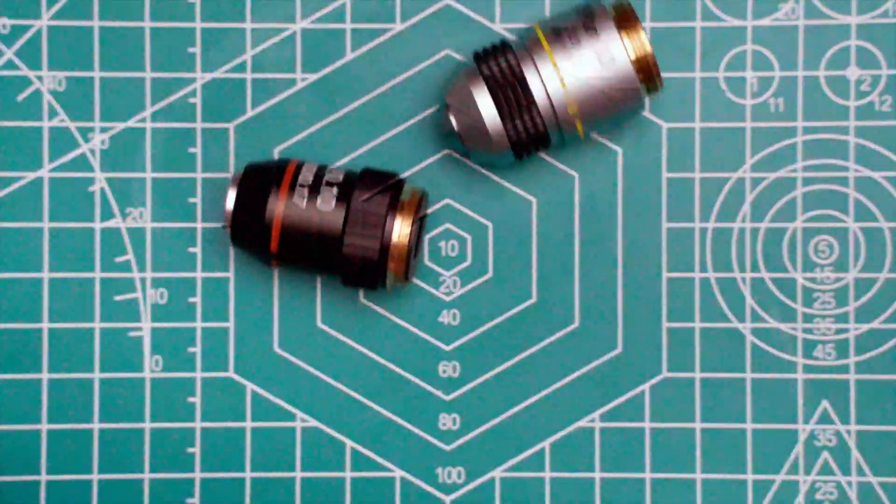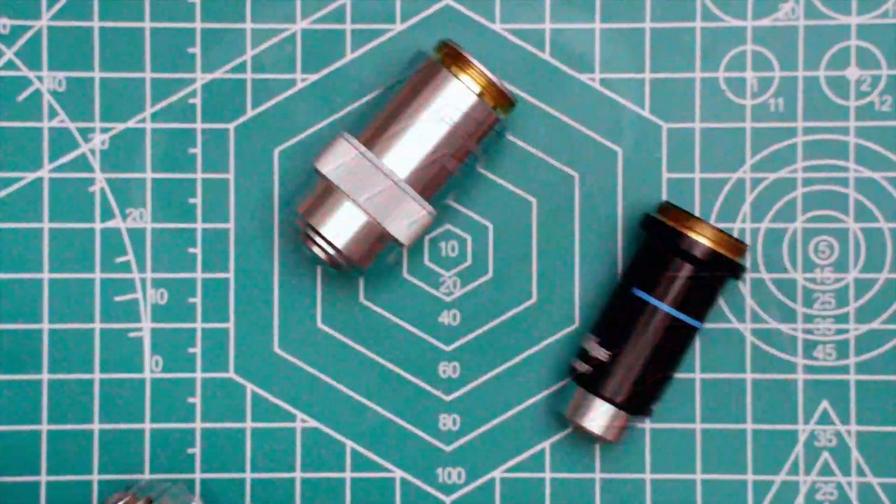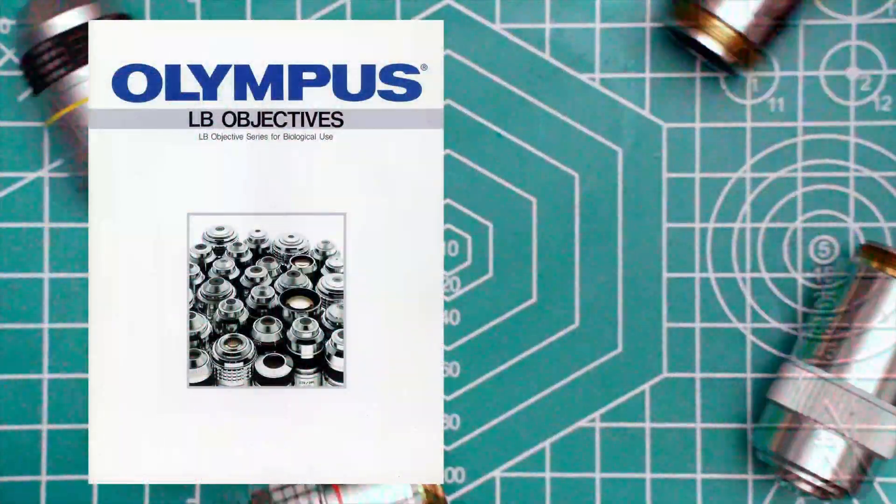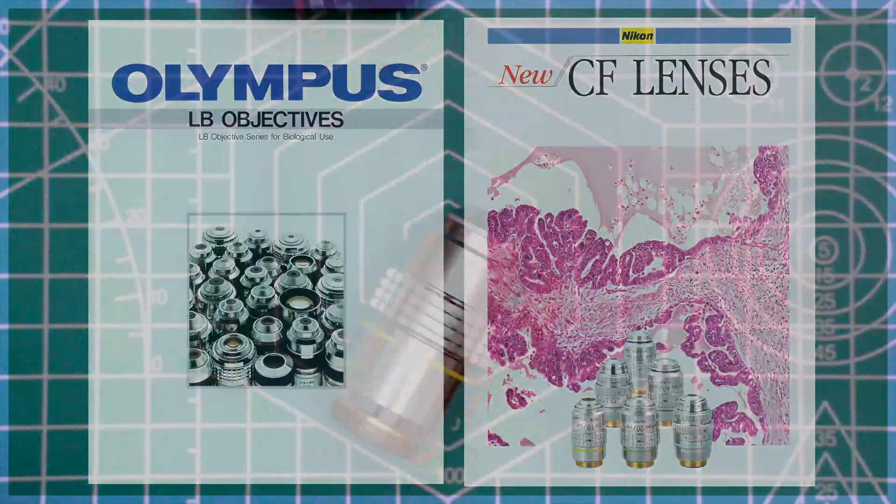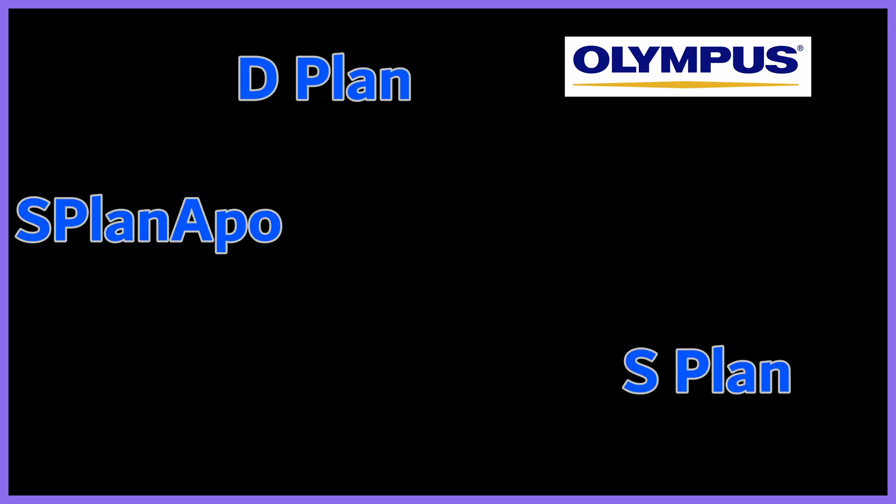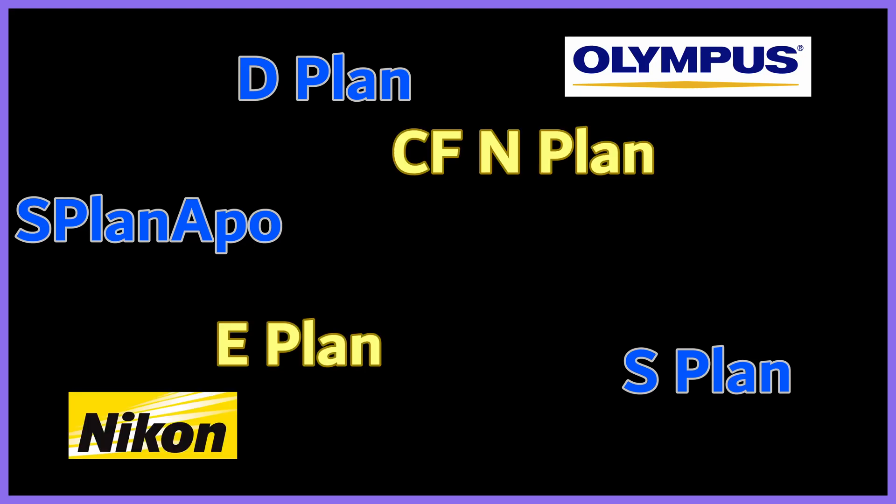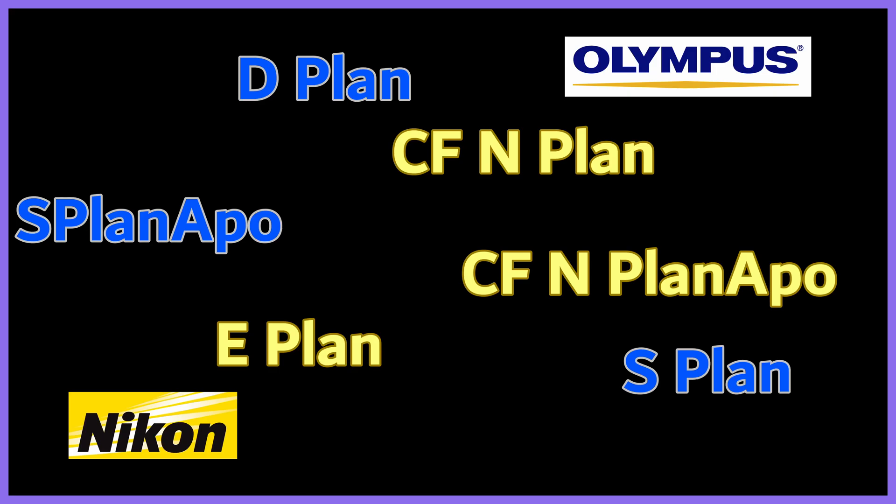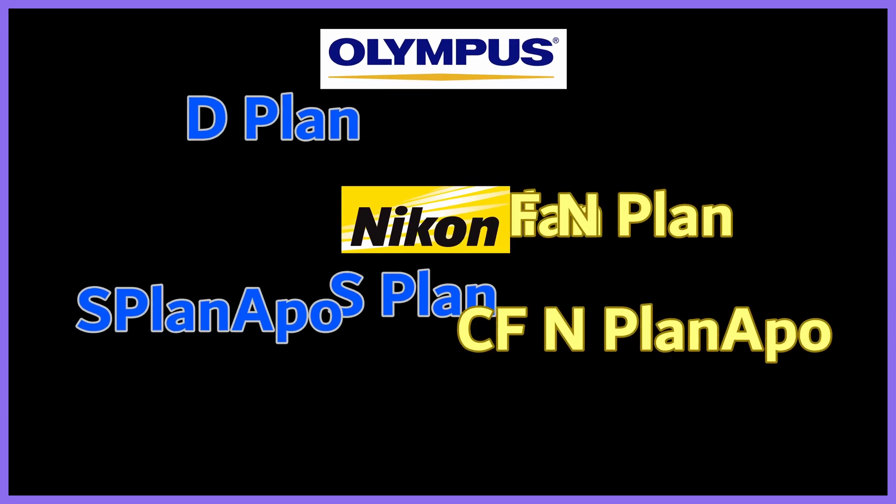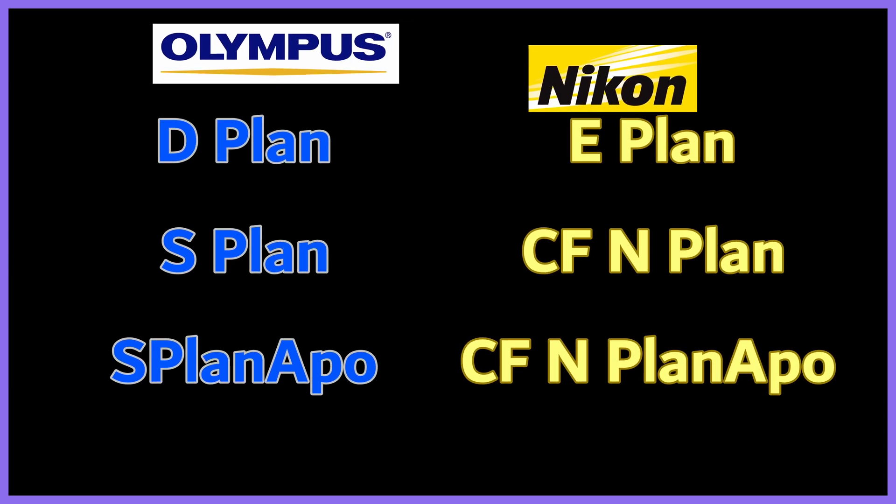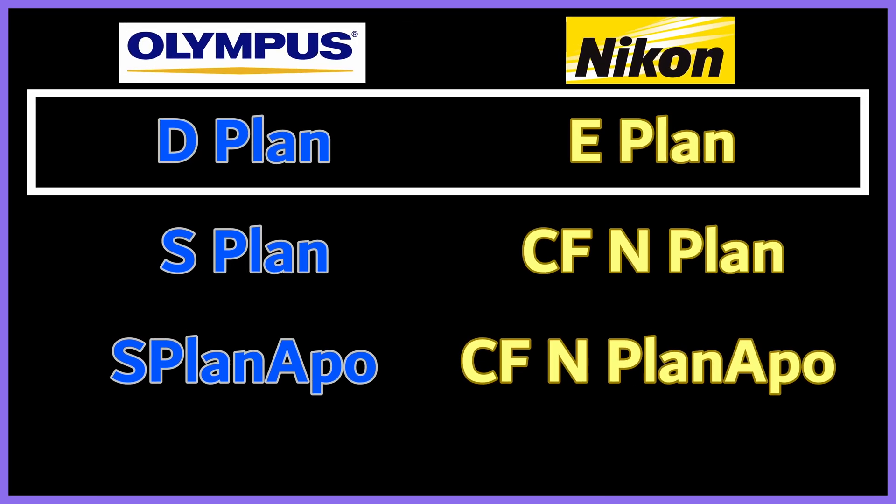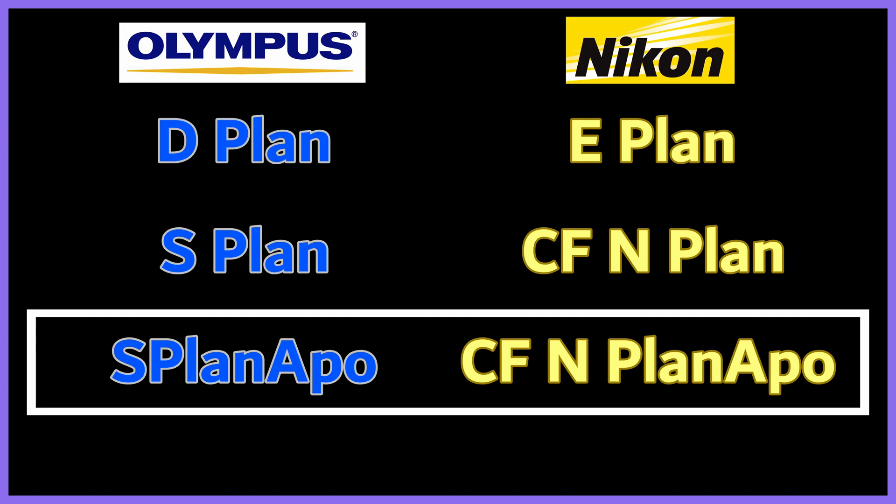So for today, I'm going to limit you to a small set of objectives from two different manufacturers: Olympus and Nikon. The objectives I recommend for you are Olympus's D-Plan, S-Plan, or S-Plan Apo Brightfield objectives, or Nikon's E-Plan, CFN-Plan, or CFN-Plan Apo Brightfield objectives. These are roughly organized into similar product classes, which I refer to as low-end plans, high-end plans, and high-end plan apochromats.